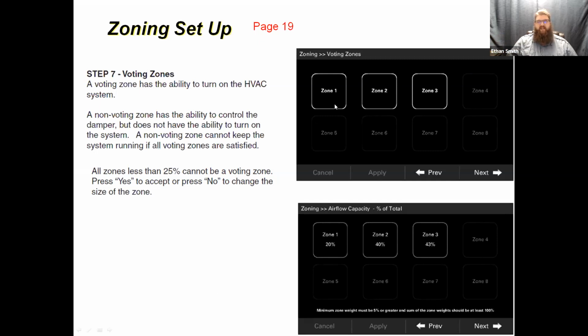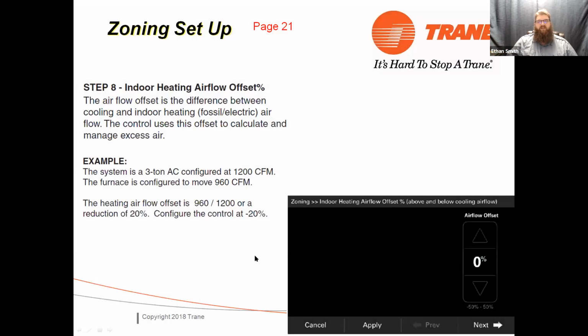Okay, so once we get past zone size and voting zones, it's going to get you into the heating airflow offset. So this is really important if you run into a situation where your airflow for your heat and your airflow for your cooling are dramatically different. So if we have a 3-ton AC on a 60,000 BTU furnace, that 60,000 BTU furnace only wants to run 960 CFM maximum, but our AC is going to want to run 1200 CFM. It calculates our zone sizes based on our outdoor unit airflow. So in this case, we've got a negative airflow offset of 20% because my furnace is roughly moving 20% less air than the air conditioner. So we would set our airflow offset to negative 20% in this case.